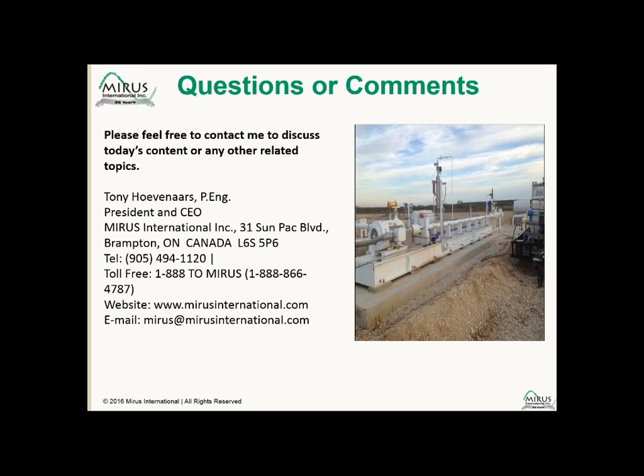Please explain further about doubling the size of the generator feeding nonlinear loads. I did sort of answer that a couple of questions back. This is the same person that asked the previous question about the 4 500 horsepower motors. In that application, if you're only putting a line reactor and no further mitigation, that's quite a bit more than 25% nonlinear load. That's really about 80% nonlinear load. So a 2,000 kilowatt generator wouldn't work. You would need to go at least 2.5 times that load if you weren't putting in harmonic mitigation. So as I said earlier, you would require about a 5,000 kilowatt generator in that application.